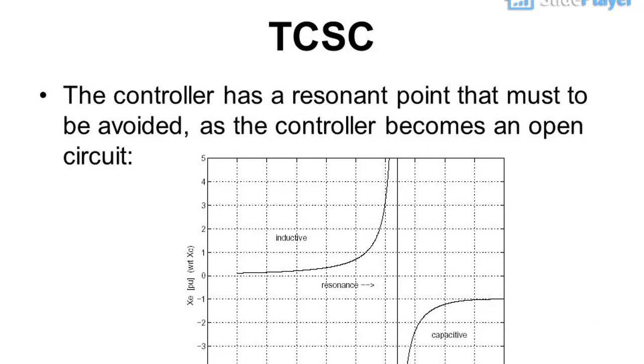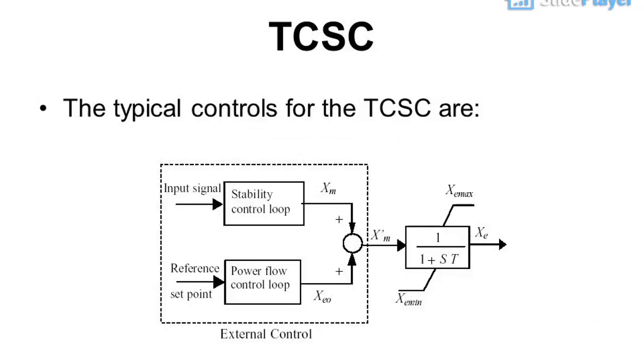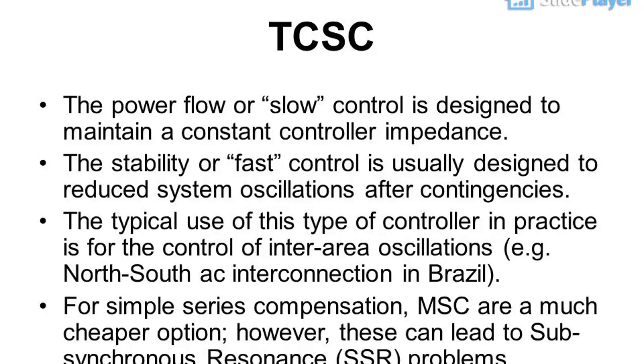TCSC: the controller has a resonant point that must be avoided, as the controller becomes an open circuit. The typical controls for the TCSC are: the power flow or slow control, designed to maintain a constant controller impedance; and the stability or fast control, usually designed to reduce system oscillations after contingencies. The typical use is for the control of inter-area oscillations, for example the north-south AC interconnection in Brazil.